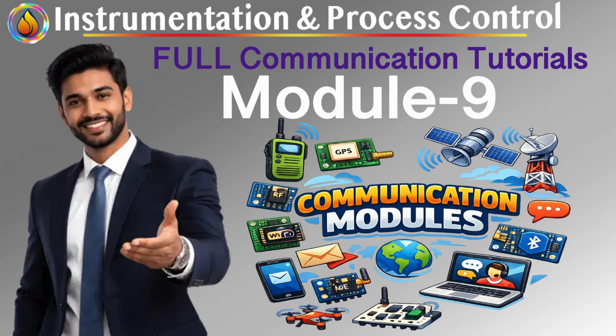Startup behavior, where this really pays off. Remember episode 9.1 and startup current? Here's where loop-based design quietly saves you. Different loops have different startup characteristics. Control valves may surge, analyzers may warm up, transmitters may stabilize at different rates. When you mix loops on one segment, startup currents stack unpredictably, voltage dips propagate across unrelated loops, commissioning becomes chaotic. When loops are isolated, startup behavior is contained, power margins are clearer, and "it only fails on restart" problems disappear.